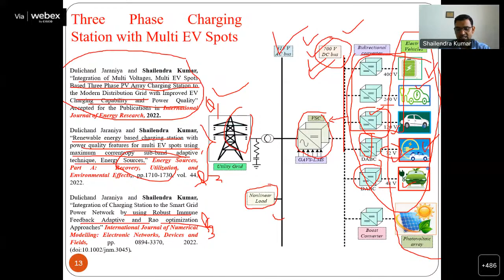Sometimes we have to buck the voltage from 700 to 72 volt when we require to charge. And sometimes a 72 volt vehicle needs to connect to the DC bus, so we require to boost the voltage from 72 volt to 700. A normal boost converter or normal bidirectional non-isolated converter will not work at that moment, or will have significant losses, or you may damage the switches. So it is not recommended; high gain converters are required in that case.